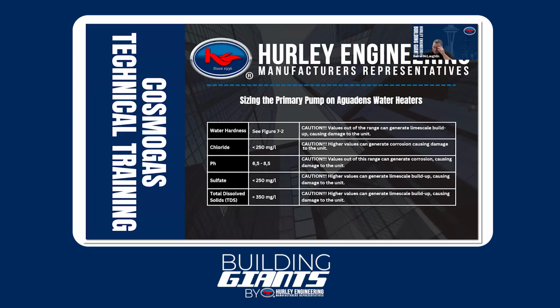You know, if you're out in a remote site or a rural site, maybe they're on well water, things like that. Now it might be in your best interest to take a sample, get it processed, and find out what their actual values are. But we want to see things like water hardness, pH, sulfate, total dissolved solids, all of these things combined. If we can get under the right levels, we've got a much better chance of having success with regards to low scale buildup and low corrosion. So these are CosmoGas's recommendations of where your water quality needs to be to have the most success with their boilers.